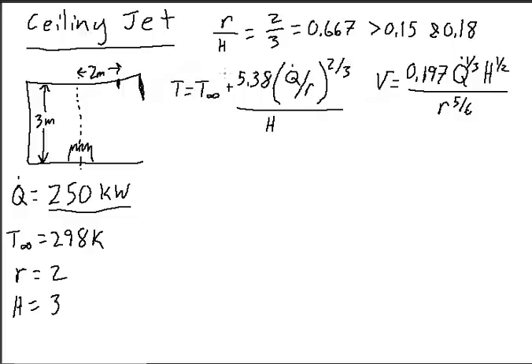So first thing we need to do is calculate an R over H value. I've written out part of this analysis already to save time in the video. But the R over H value will tell you which set of Alpert's correlations equations to use. So in this case we use 2 over 3 which equals 0.667 approximately, and that's greater than both 0.15 and 0.18.